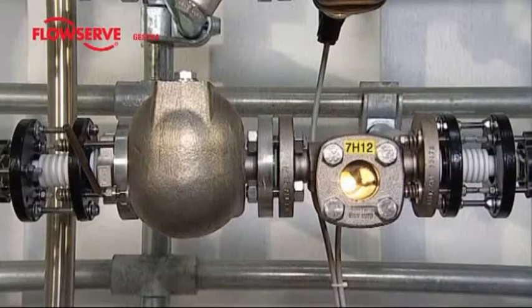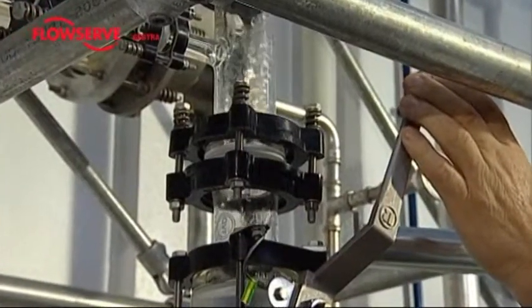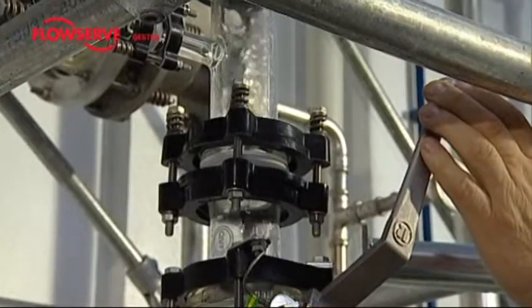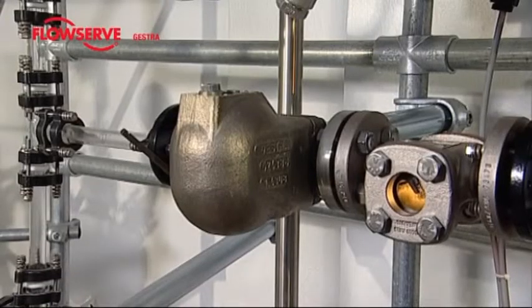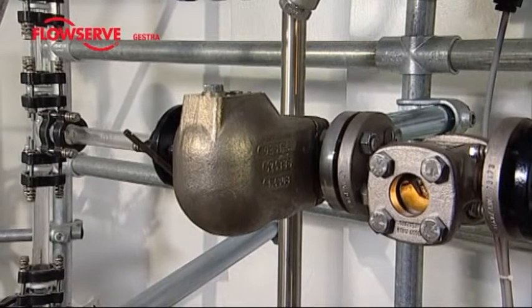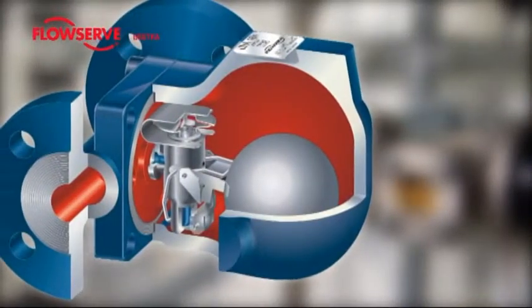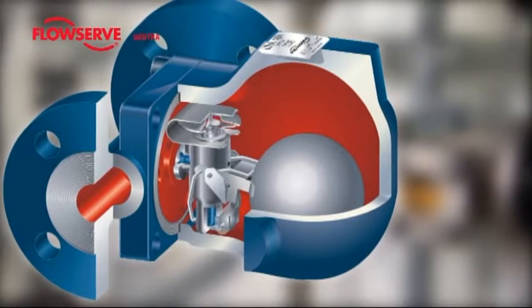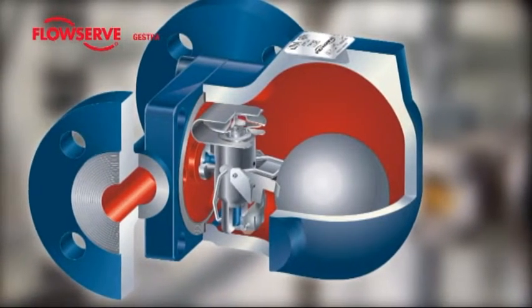If the steam is controlled and the steam pressure varies as a result, this will have hardly any influence on the condensate discharge, which will still be controlled solely by the level in the trap, independently of pressure and temperature. Owing to the large volume offered by the body of a ball float trap, fluctuations in flow rate can be handled easily. The steam trap is not prone to hiccups.